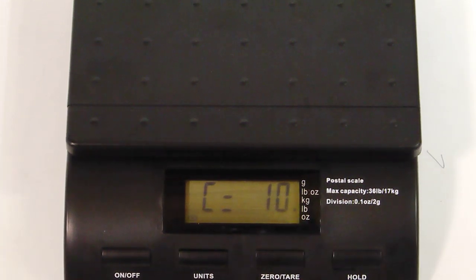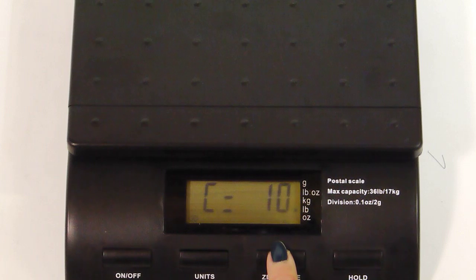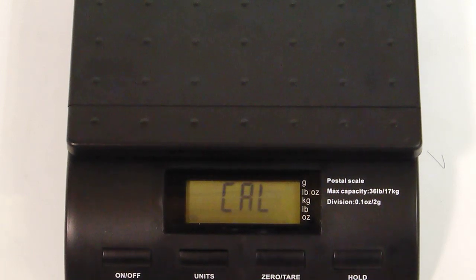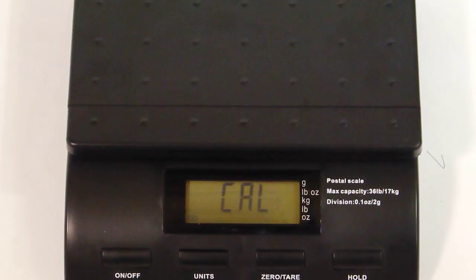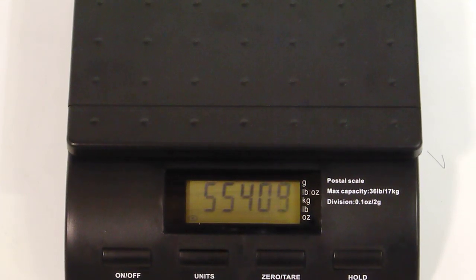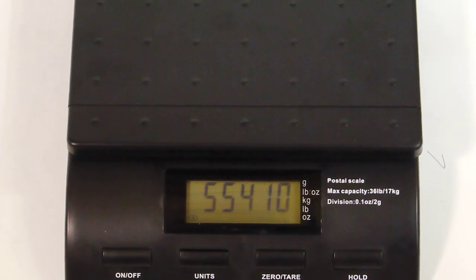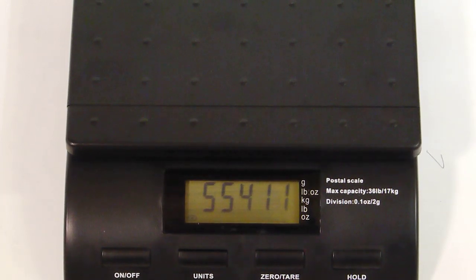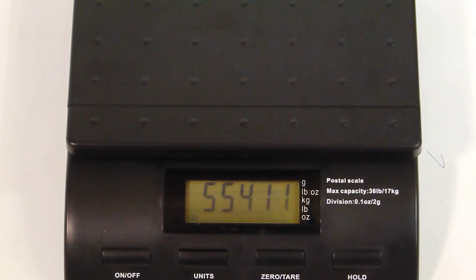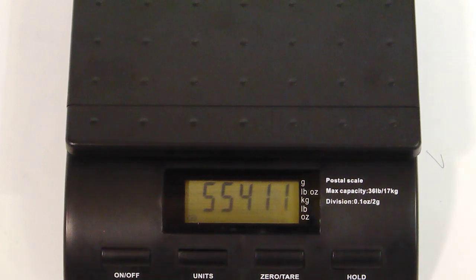Stop at 10 pounds and next press the zero/tare key and you will see Cal. Then a 5-digit A/D value which is the internal digital count on the scale. It should be stable within plus or minus 5 counts. This is good.